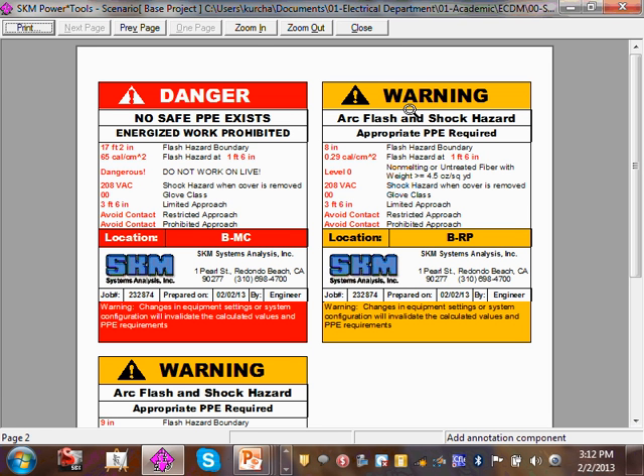Look at the arc flash boundary, guys. Flash boundary is 17 feet. And the reason for this, because there's no fuse to protect me. This is the meter socket. We're talking about the meter socket here. For a 500 amp, there is no circuit breaker ahead of it. Now, if there is a fuse or a circuit breaker ahead of it, it will knock it down to a lower value. If you guys look at this one, this is RP for the receptacle panel. My arc flash boundary is 8 inches. Level 0, cotton shirts, glasses. You don't even need a shield for category 0, right? No shield.